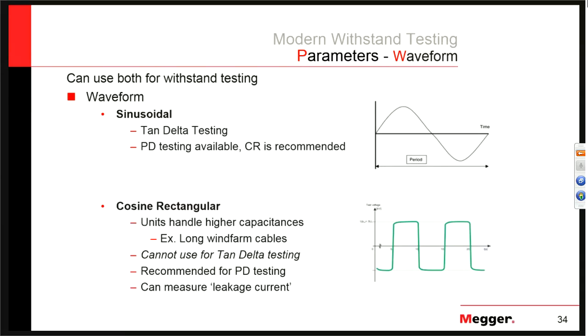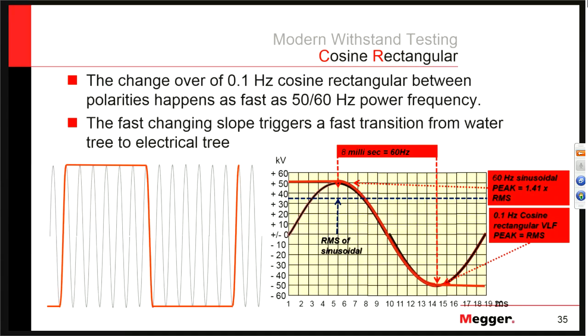Zooming in on the cosine rectangular waveform: it is 0.1 Hz VLF, but at the transition from positive to negative periods, the waveform is shaped to mimic power frequency. Based on the capacitance of the cable, that transition can switch in about 8 to 10 milliseconds — very similar to the change in polarity of 50 or 60 Hz power frequency testing. So we get the benefits of lower power consumption while also keeping the benefits of power frequency testing in that fast voltage transition.